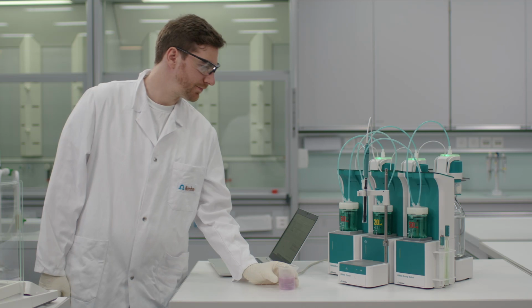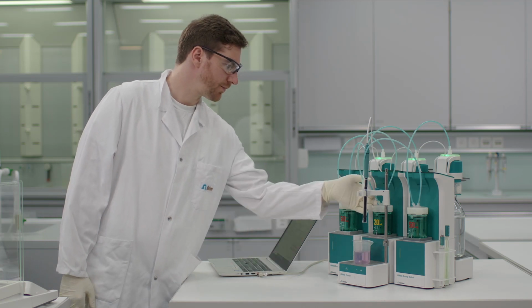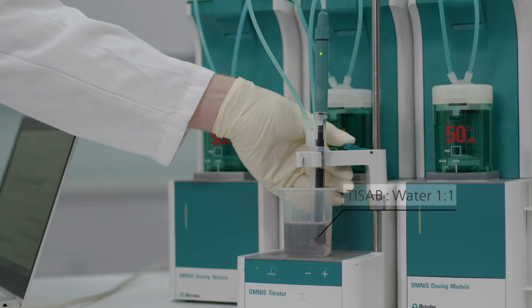No matter if you do a sensor calibration, a sample measurement or a standard addition, you must condition the electrode before each measurement. To do so, place the electrode in a beaker filled with a mixture of 1:1 TISAB and deionized water for 2 minutes.